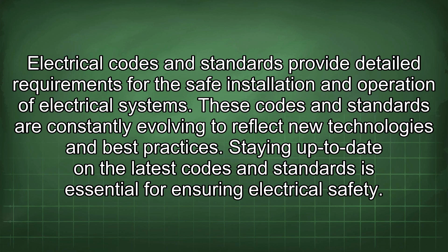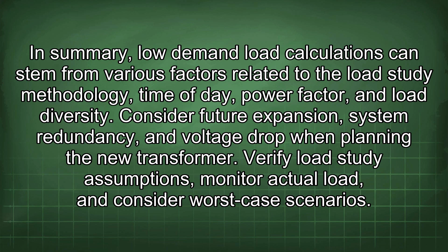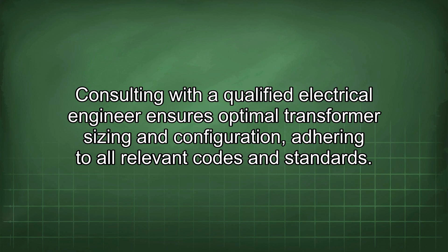In summary, demand load calculations can vary due to various factors related to the load study methodology, time of day, power factor, and load diversity. Consider future expansion, system redundancy, and voltage drop when planning the new transformer. Verify load study assumptions, monitor actual load, and consider worst-case scenarios. Consulting with a qualified electrical engineer ensures optimal transformer sizing and configuration, adhering to all relevant codes and standards.